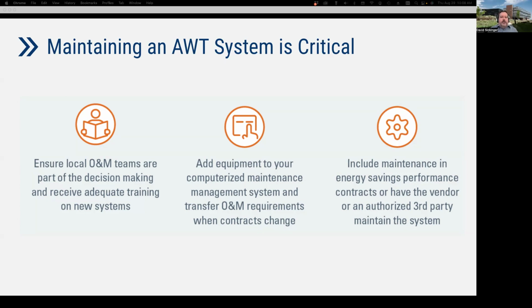Second, make sure the AWT system is added to the CMMS, the computerized maintenance management system, so O&M is maintained if contracts change. There have been a few cases where that's been an issue. So good takeaway, lesson learned. And then a recent AWT project reinforced the importance of properly maintaining cooling tower systems, as that impacts both performance of the AWT and chemical water treatment systems. So the suggestion is to consider including maintenance in energy savings performance contracts or by an authorized third-party water treatment company. Next slide, please.